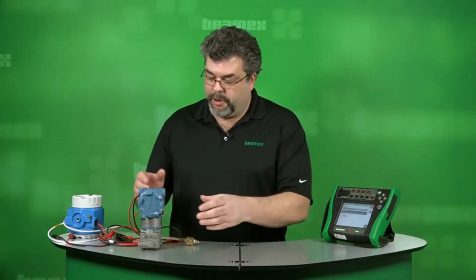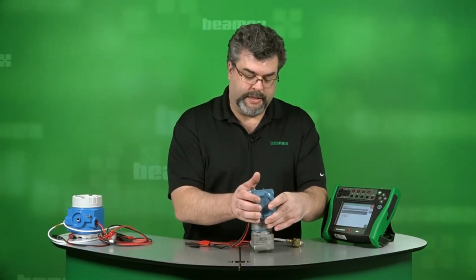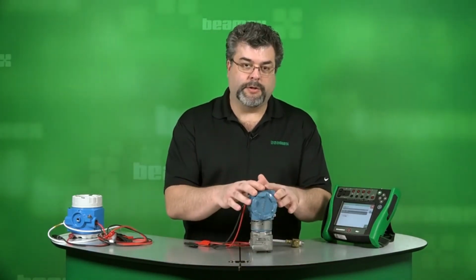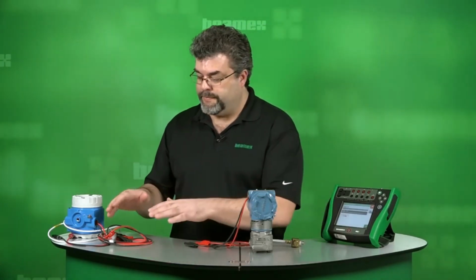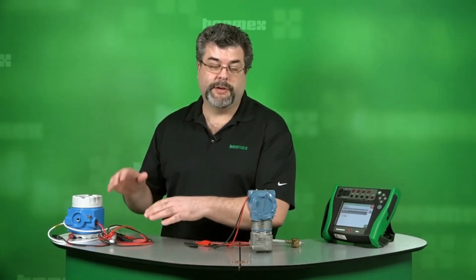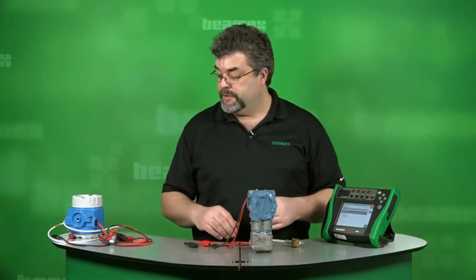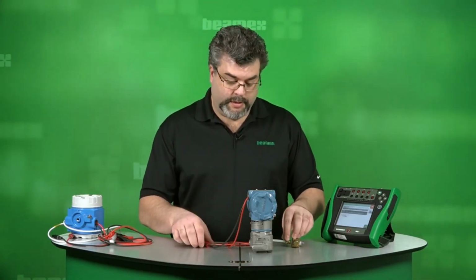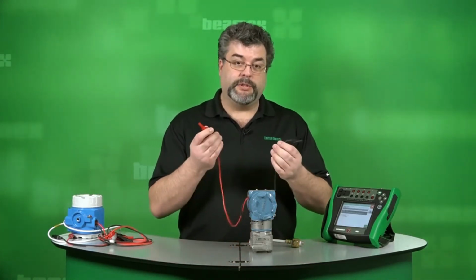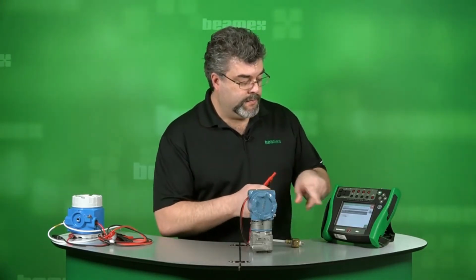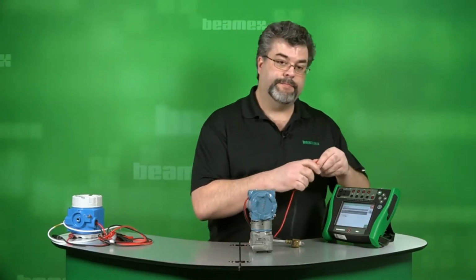Now let's make a connection. If we connect HART, let's hook up this pressure transmitter. And we actually have a HART transmitter that's pressure. We have a Profibus temperature transmitter. And we also have a Foundation Fieldbus temperature transmitter. Now I'm new at this. I don't know where to hook up. I look, here's where I connect.